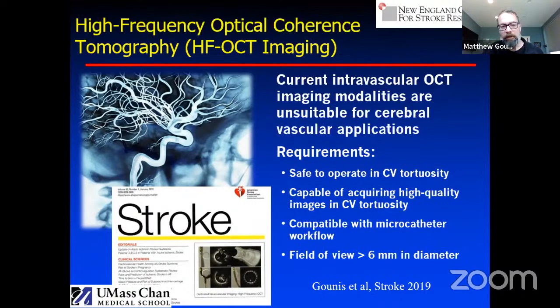So we set out in 2014-15 with a collaboration of a local company here in Sudbury, Massachusetts, called Gentuity, to create a neurovascular optical coherence tomography system. The first thing you do when you're trying to make a new device is you set up what's called your technical design requirements. And so obviously the first thing that we wanted is a safe system to operate in representative tortuosity of the cerebrovascular system, capable of acquiring high quality images. So that's the efficacy metric, right? Including representative tortuosity. We set out that it has to be compatible with microcatheter workflow. So we need a really small system that we can put through a microcatheter. And we'd like a field of view to be at least 6 millimeters.